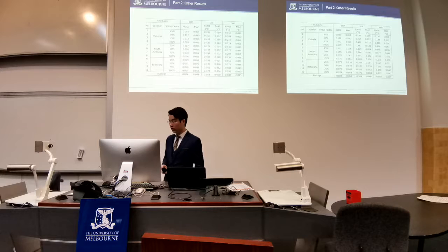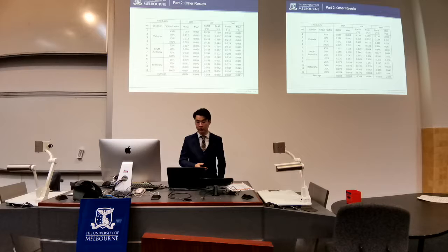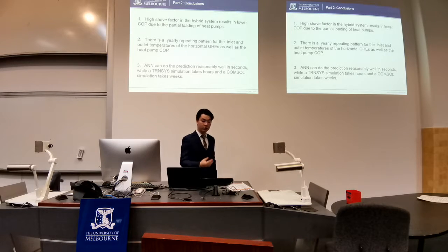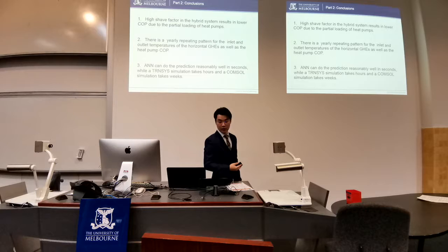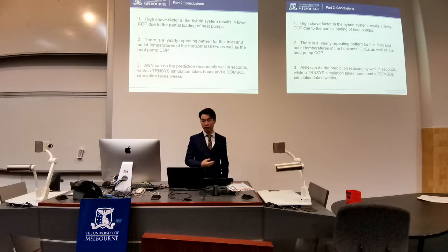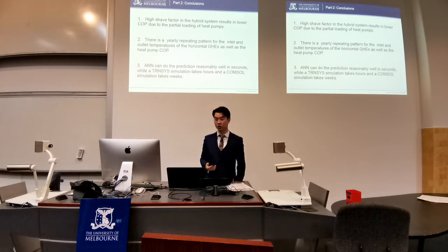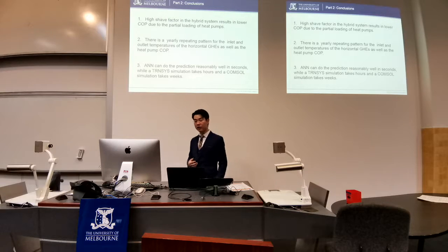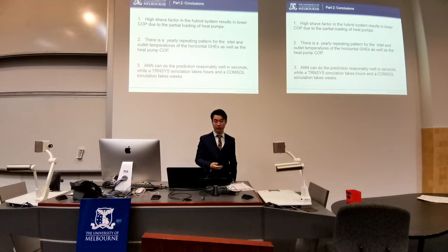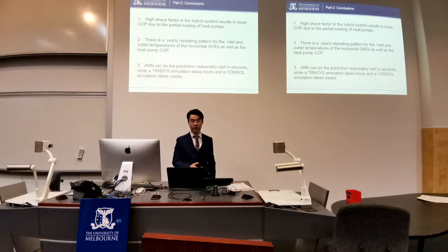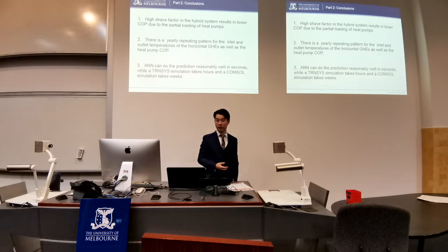I've also done a lot of other analysis here, showing quite consistent results, and based on this I've drawn some conclusions. First, a high shave factor in the hybrid system could result in a lower COP due to partial loading of heat pumps. Second, there's a yearly repeating pattern for the inlet and outlet temperatures of horizontal ground heat exchangers, as well as the heat pump COP. Last but not least, the ANN can make predictions reasonably well in seconds, while a TRNSYS simulation could take hours and a COMSOL simulation could take weeks.